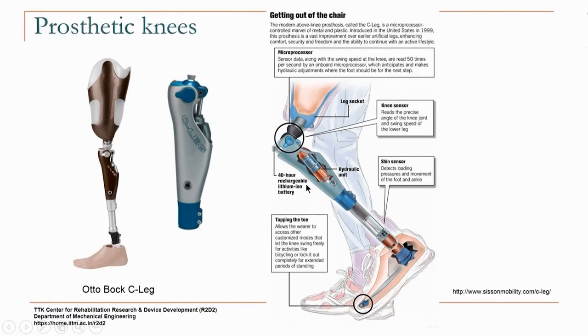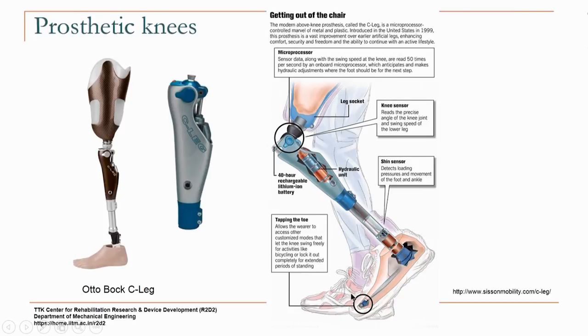The C-leg has a rechargeable battery and the microprocessor reads sensor data at 50 Hz — 50 times per second. If the user wants to do other activities, there is a switch activated by tapping the toe. The knee can be programmed with different programs; for instance, if they want to bicycle they will tap the toe to activate that program.